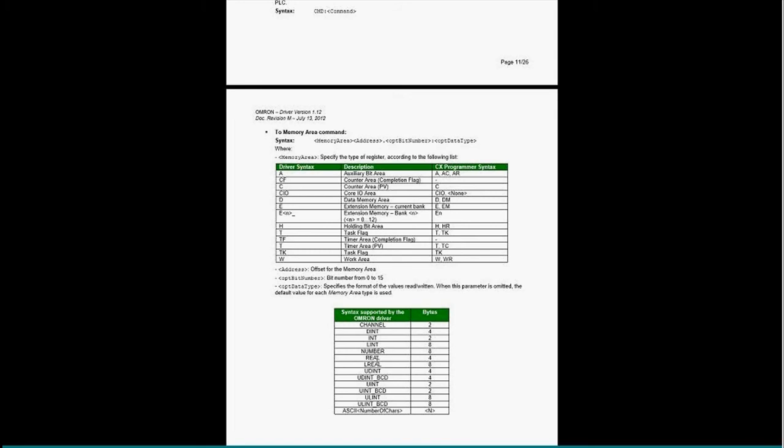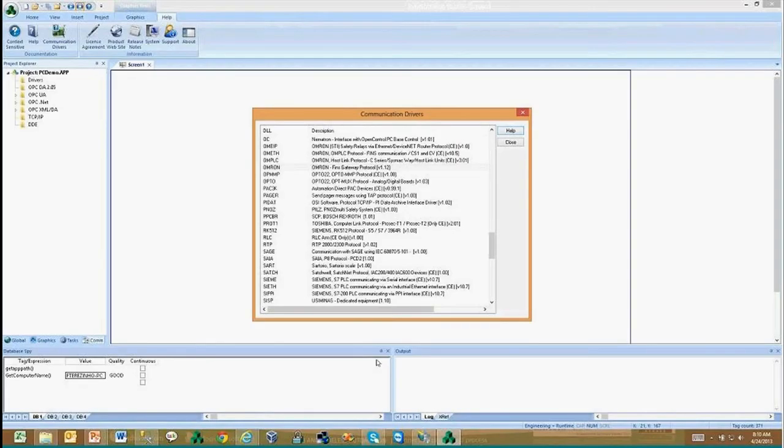If you communicate with a PLC like the NJ or CJ2 that supports tag names instead of memory address, you just configure the driver worksheet to read a tag which happens to be a floating point in the PLC, and we automatically read it as a floating point. You just have to assign a real tag on the InduSoft side to exchange data with that Omron tag, and you'll be able to read it as a floating point.